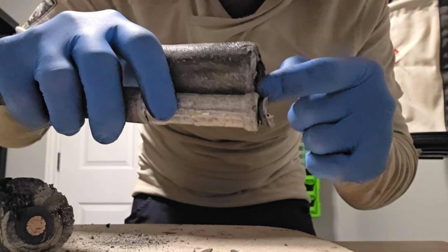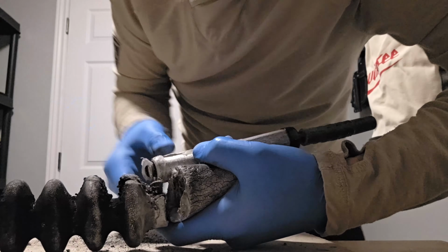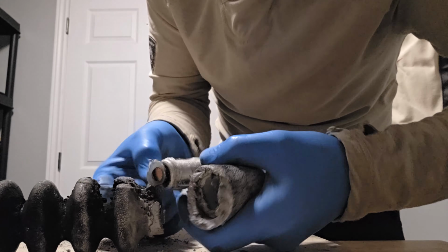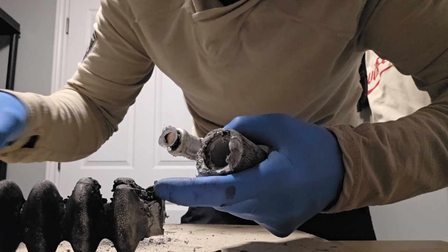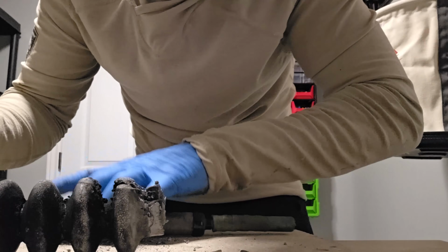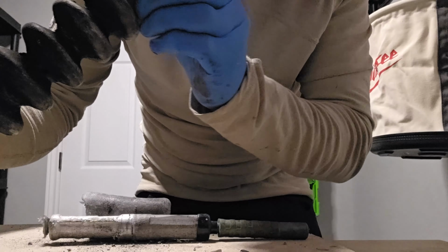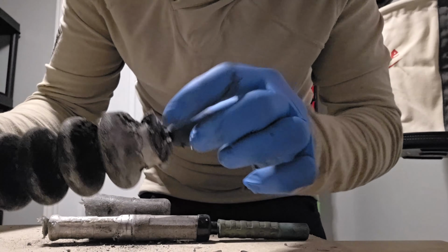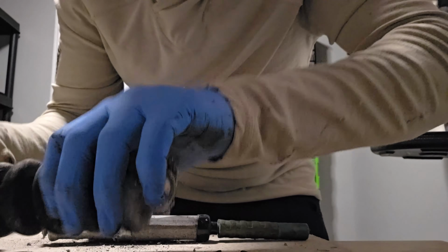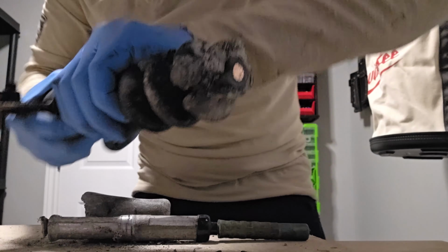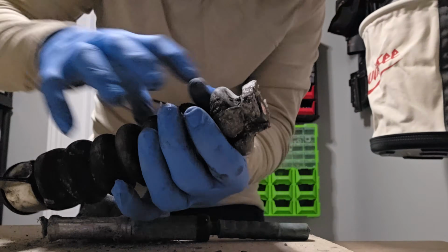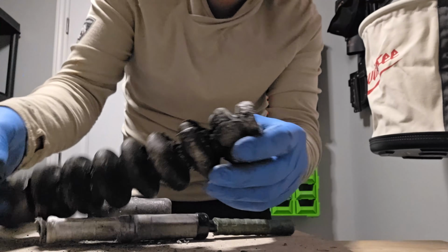So that being energized at 7,200 volts, it looked like there was just a complete breakdown of the insulator. And it must have been tracking through that, slowly burning and establishing a path to ground. So the cable itself never really failed. It was literally the degradation of the termination.